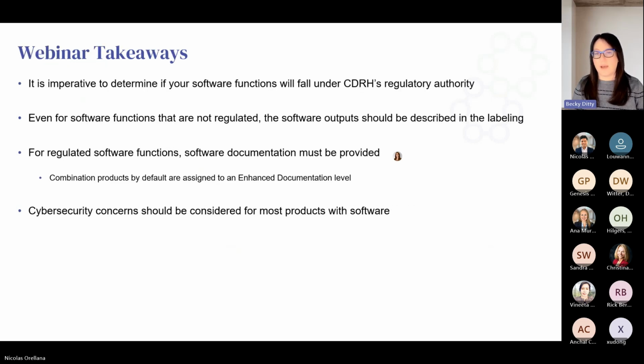So in summary from this webinar, it's imperative to determine if your software functions are regulated. And if they aren't, you still need to describe the software outputs in your labeling for combination products. And for regulated software products, make sure that you are providing all the software documentation, that you're typically falling into the enhanced documentation level. And if you think it's something less than that, then you really should discuss that in a pre-submission with FDA. And then cybersecurity really pretty much applies to any device if it's got software.